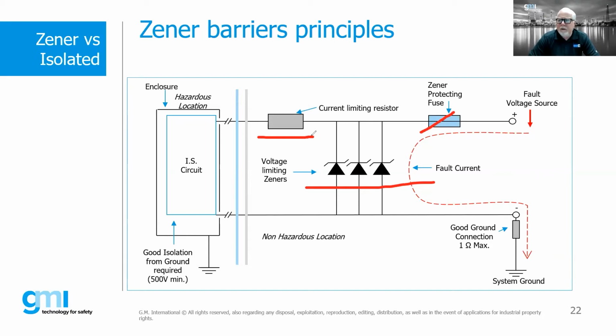If we have a fault condition, say coming from our control panel, maybe a bit of an inrush, the Zener diodes will open up and divert any excess voltage. So say this barrier is rated at 28 volts maximum - the Zener diodes are basically put in parallel and allow the excess voltage to go to ground.